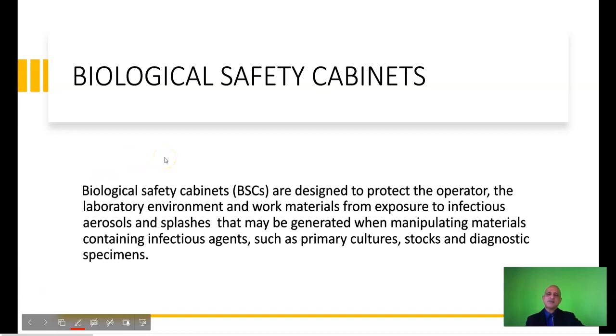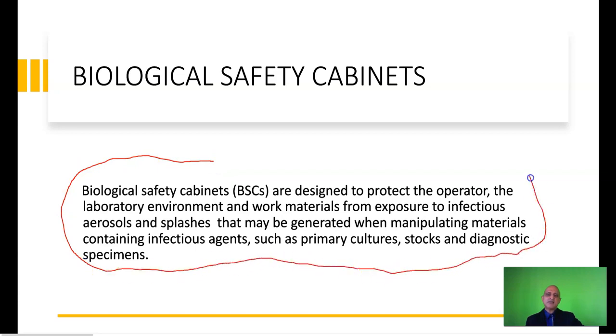One of the laboratory equipment which has been described in detail is the biological safety cabinet. Biological safety cabinets are designed to protect the operator, the laboratory environment, and work material from exposure to infectious aerosols and splashes that may be generated when manipulating materials containing infectious agents such as primary cultures, stocks, and diagnostic specimens. What a biological safety cabinet offers you is a safe working space. However, in order to utilize a biological safety cabinet, one has to take into account certain precautions such as the administrative controls and standard operating procedures.